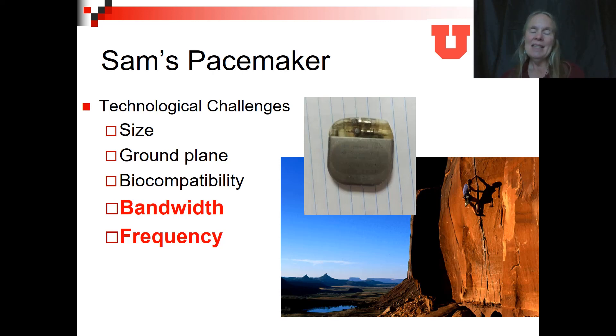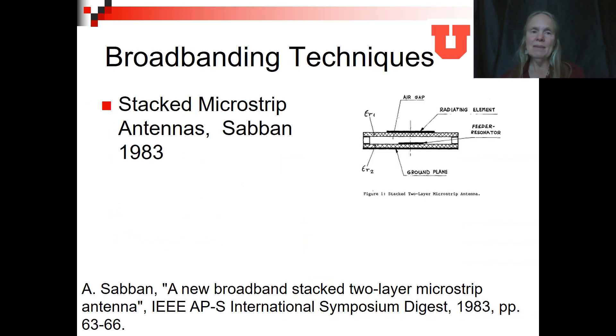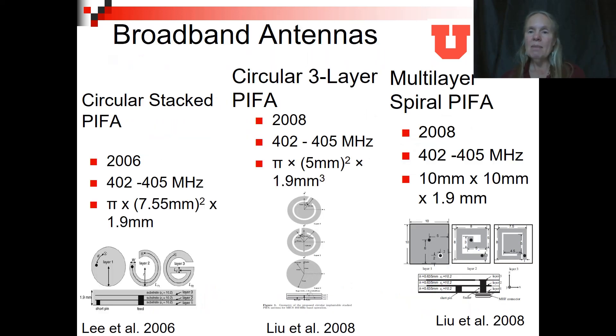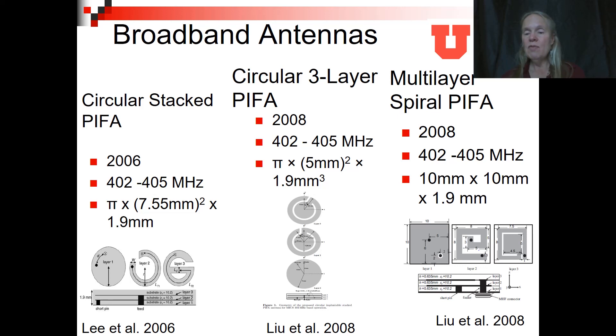Looking again at Sam's pacemaker and the issues with bandwidth and frequency: these designs had very little bandwidth — they were very narrow band. Stacked microstrip antennas had been developed in 1983 for non-biological broadbanding, and this was quickly picked up in bioelectromagnetics. Designs in 2006 and 2008 showed different broader-band antenna designs. The concept of broadbanding was to provide multiple current paths of different lengths, so that a low frequency takes a long path and a high frequency resonates on a short path. These physical structures accomplish that goal.